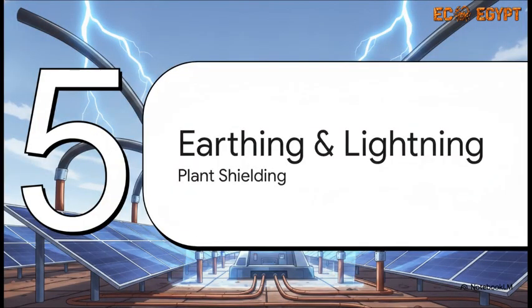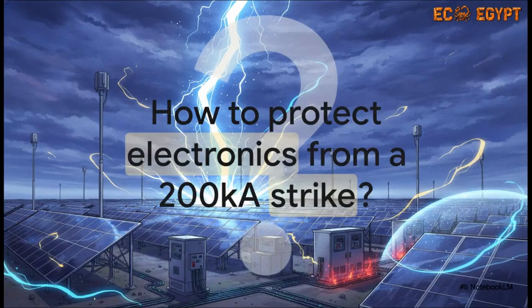That brings us to Section 5, Earthing and Lightning Protection. So a utility-scale solar plant is essentially a massive, wide-open field filled with metal structures and highly sensitive electronics. Basically, it's prime real estate for a lightning strike. So, how exactly do you protect a 60-megawatt plant from a direct strike that can unleash up to 200,000 amps of pure destructive energy? I mean, without protection, a strike like that would start fires, completely destroy the inverters and SCADA panels, and send lethal overvoltages right through the data cables.